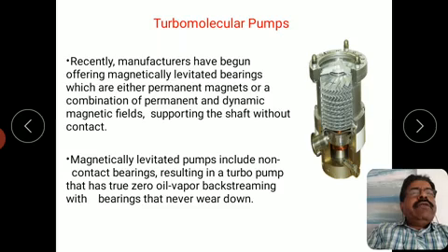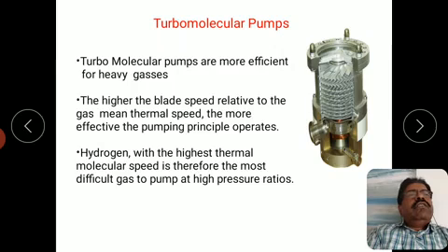So magnetically levitated pumps include non-contact bearings. Therefore, they result in a turbo pump that has true zero oil vapor backstreaming. So no lubricant is required, therefore zero backstreaming. And there is no wear and tear involved in this particular case.